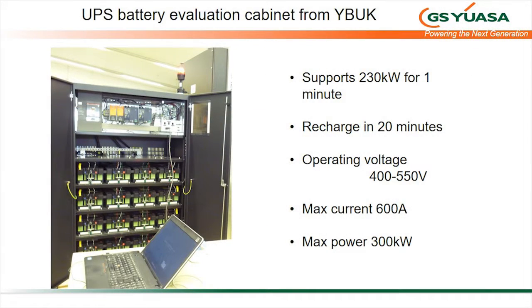Just to emphasize that, I'm showing some results from a demonstration cabinet that we can take around to customers who might want to see how lithium ion works, so they can kick the wheels, as it were, and try the system for themselves. This is a cabinet just over a meter wide, 400 millimeters deep, with up to 20 modules, so you're working up to 600 volts. That can discharge at up to 600 amps.